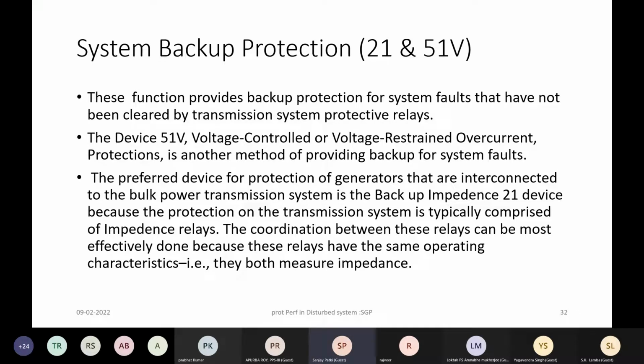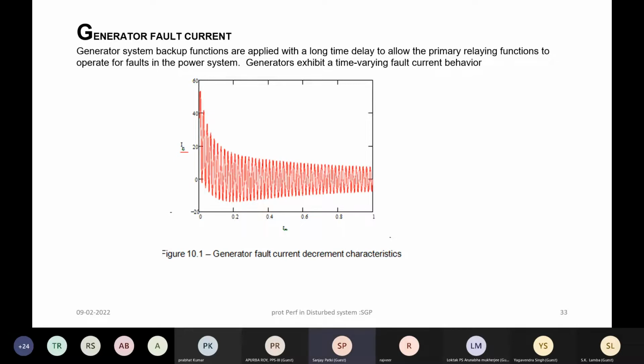Most common protection which is susceptible to have uncoordinated operation is the backup protection on the generator, the impedance relays. And we'll see that important aspect is, again, during system fault condition, impedance relays are considered to be better suited compared to the overcurrent relays, because overcurrent relays have a problem of discrimination due to the asymmetrical nature of the fault current. As we saw, the fault current has a heavy DC offset, and then gradually the fault current will come down to a steady state fault current value.